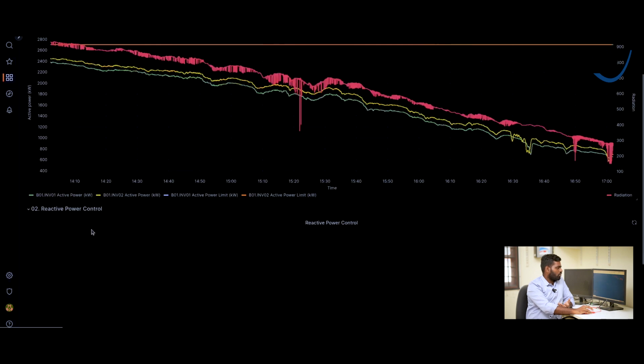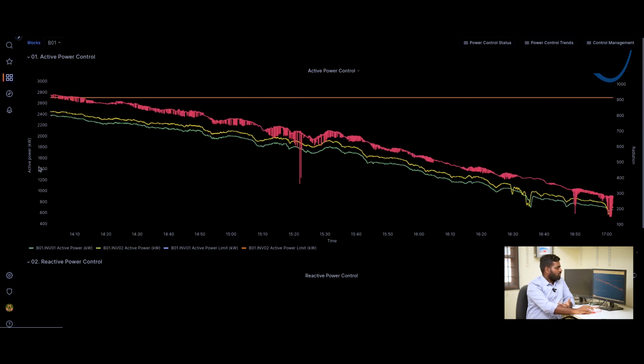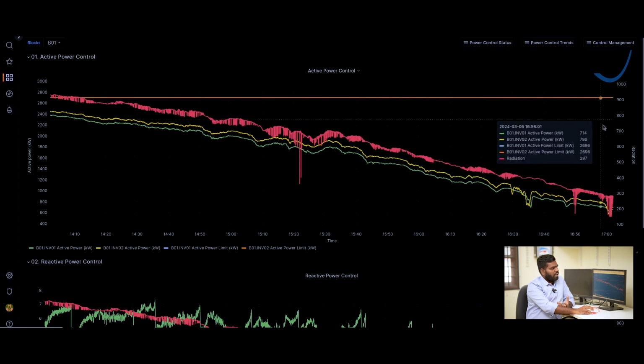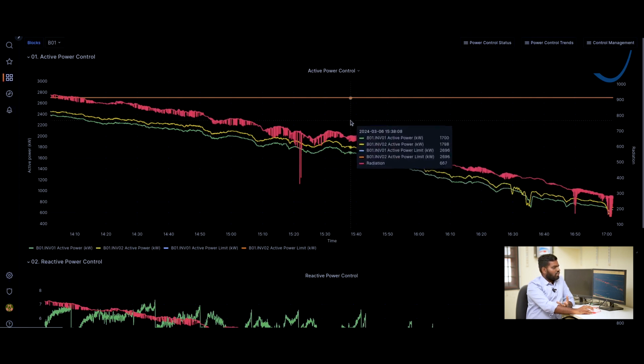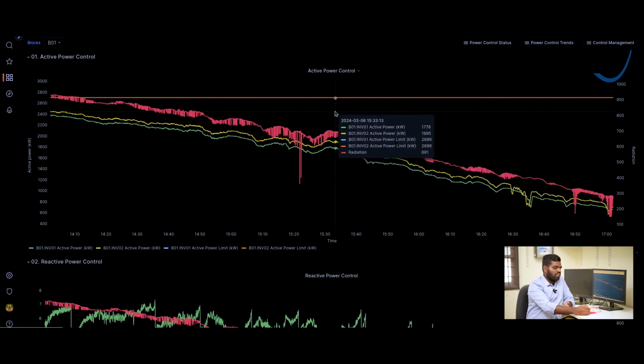This is the block wise trends. For each individual block we can check the active power control and reactive power control. In this trend screen, on the left axis we have active power, and on the right axis the radiation. Here we can check the block wise active power and its limit compared to the radiation. Block wise also we can check.